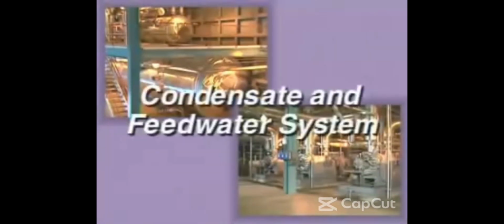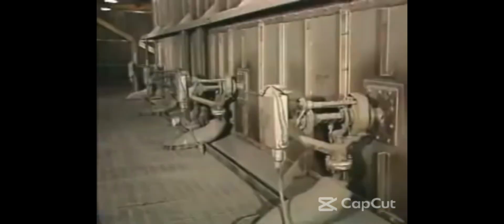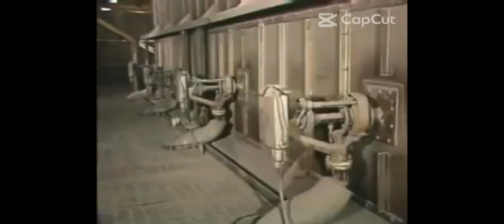Therefore, they are considered as one system, which is the condensate and feed water system. To maintain a normal operation of a ship's boiler, the water going into the boiler must be equal to the amount of steam that leaves the boiler and the main steam system.